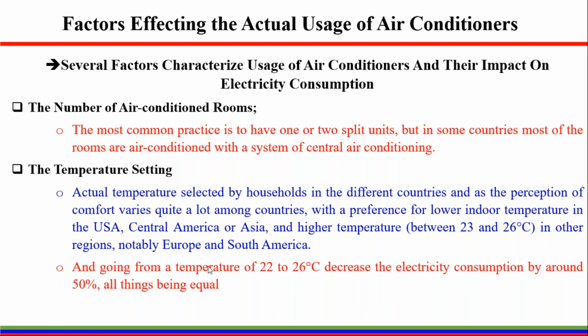Like here, it is mentioned that going from the temperature of 22 degrees centigrade to 26 degrees centigrade of the air conditioned space decreases the electricity consumption by about 50%, when all other things are equal. It means that there are the same rooms and you are using the air conditioning in one room, you set the temperature to 22 degrees, and in another room, you set the temperature to 26 degrees centigrade, it decreases the electricity consumption by around 50%.